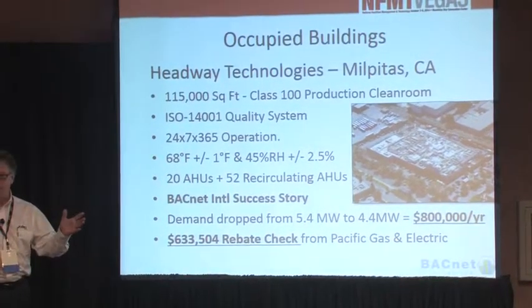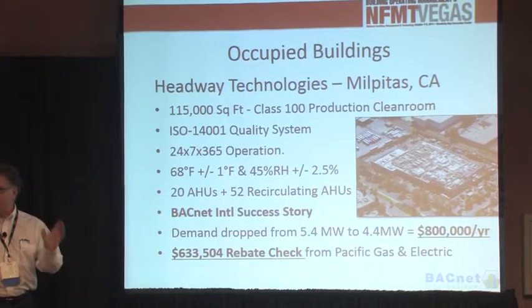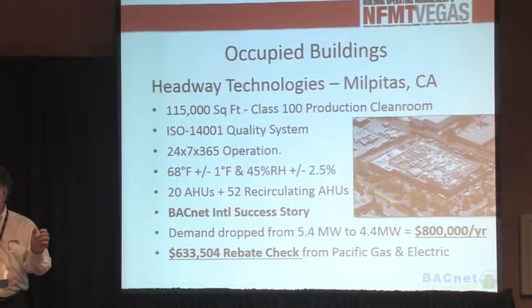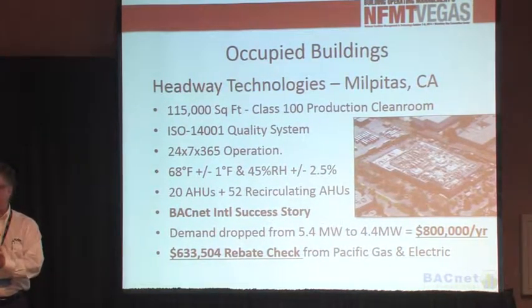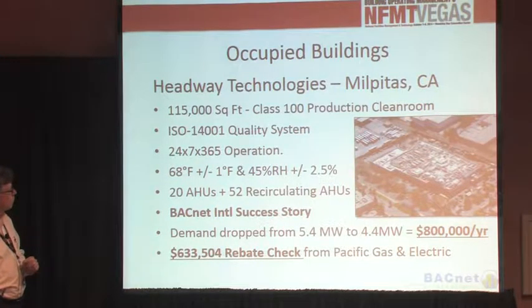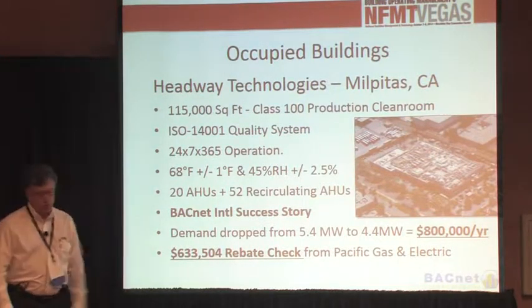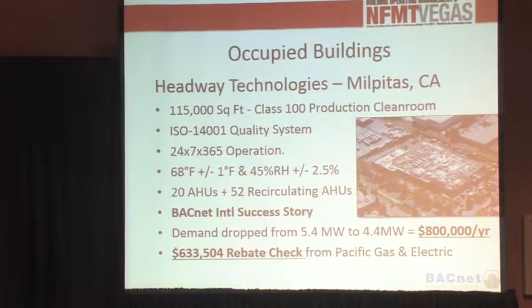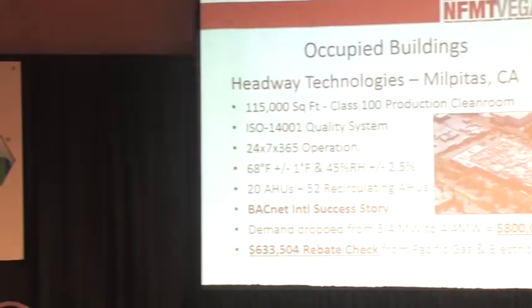So the panels all had to be built, the wire all pulled, everything ready so that they could very quickly change over some of the end devices. They had 20 air handling units that are outside air units. There were 52 air handling units that were circulating only. They had about a dozen different boilers and 6 chillers, and they were thinking they were going to have to add more boilers and chillers because a mechanical engineer came in and said your temperature control problem is you don't have enough capacity.